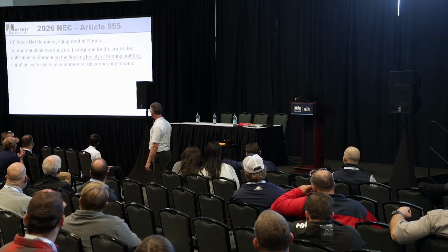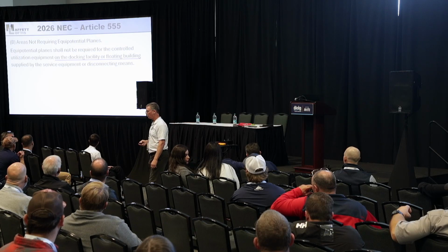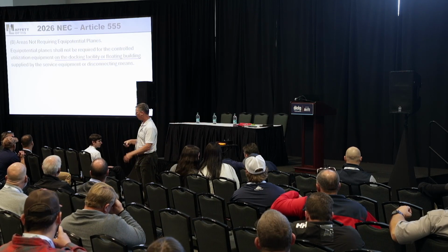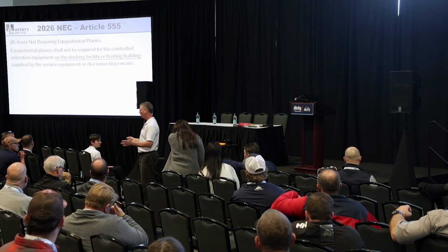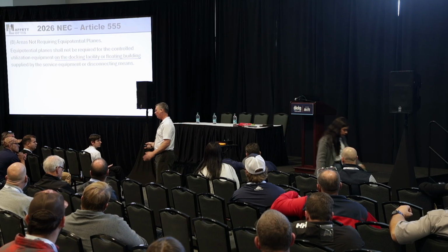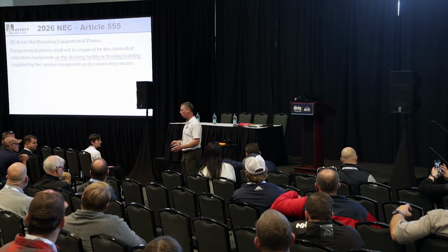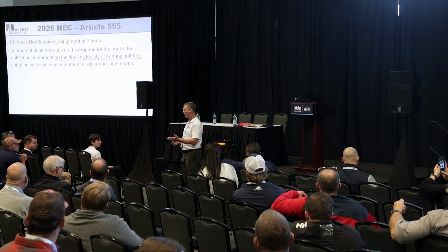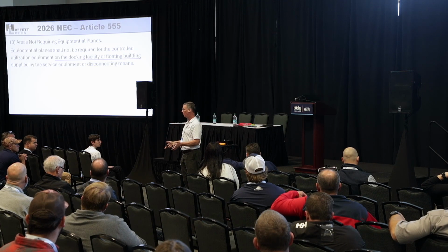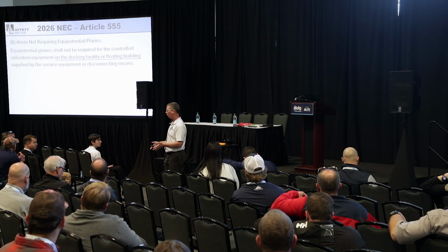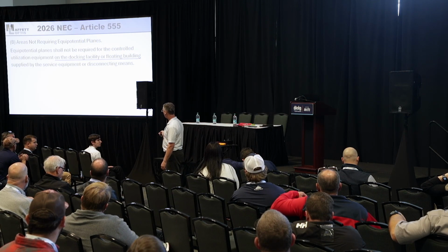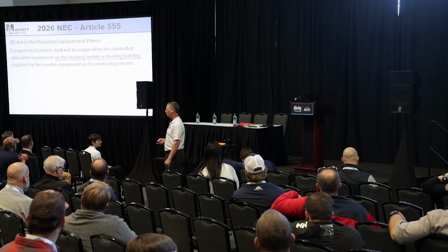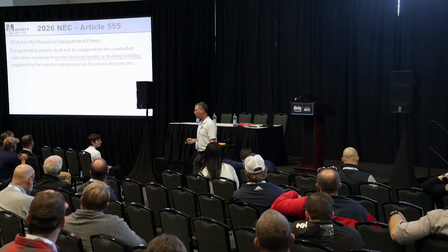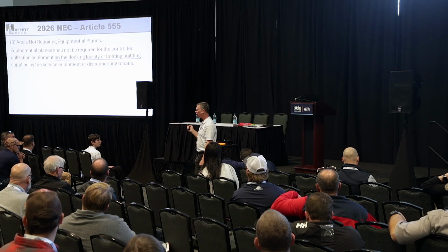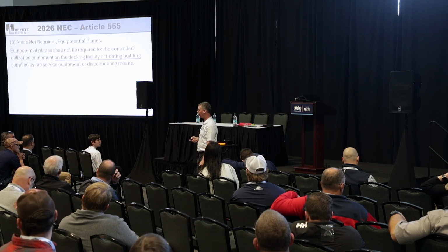If it's on the docking facility, on a floating building, you don't have to have this out on the marina, because a lot of times it's a concrete deck, wood deck, timber deck, a galvanized truss system or aluminum truss system. And if it's a galvanized metal truss system, it's going to be bonded anyway, and you already automatically have that equal potential plane out on the marina. But we're saying we're limited only to the land areas. So does that answer your question? Okay. So that's already in the code, and that's part B of that same code.